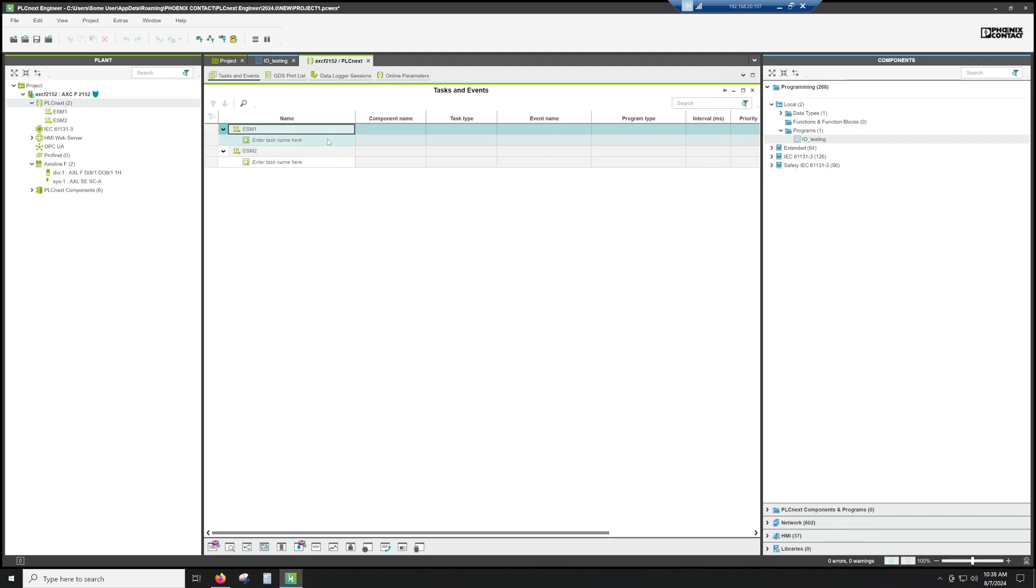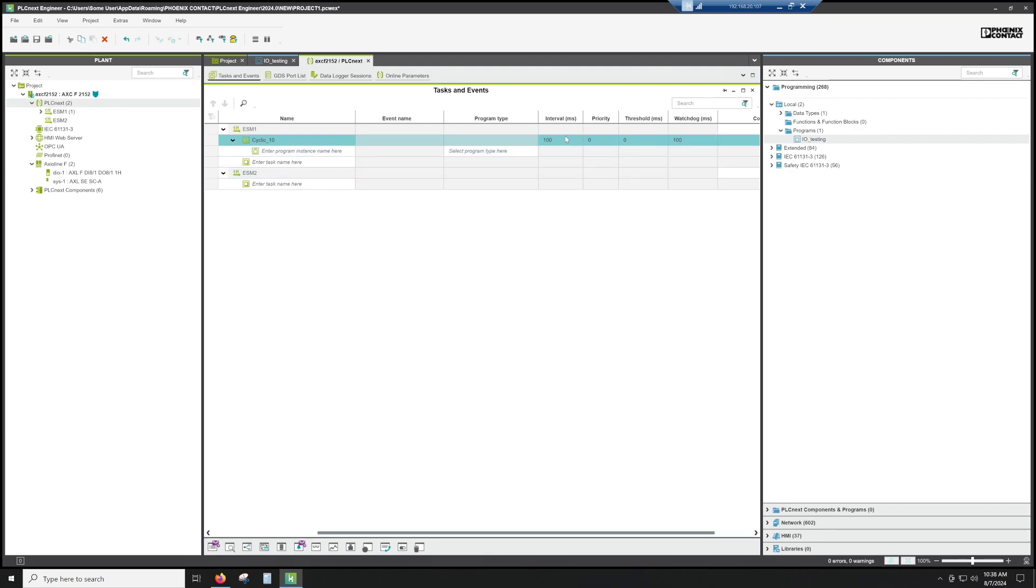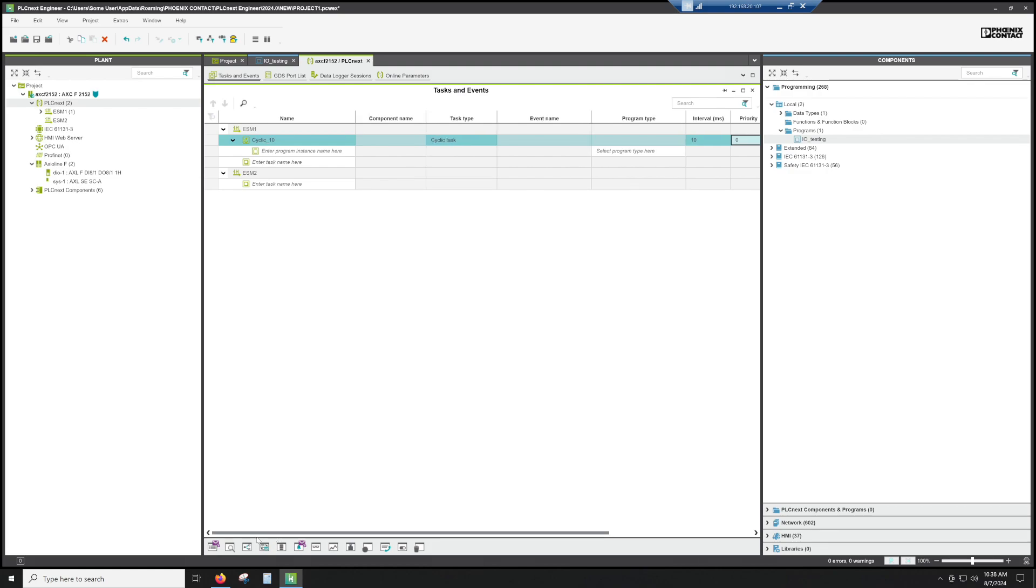There's a couple of different, there's a cyclic task. There's just a run as fast as you can task, they call it an idle task. For this, we're going to call it cyclic 10. And all that means is that we're going to make it a cyclic task and we're going to make the interval actually 10 milliseconds. So that means that every 10 milliseconds, it's going to fire that code worksheet or any task that's been put into this task.